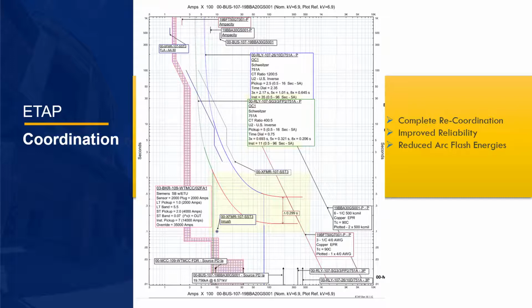To explain what we are looking at here, these curves represent the expected protective device trip curves. For the TCC, we get a visual depiction of equipment protection. In this graph, we can see that Station Service Transformer 3 is protected, and we maintain coordination as we go up the time current scales. The highlighted portion shows how the system protection is changed by enabling the maintenance mode settings, which in turn activates the instantaneous function.